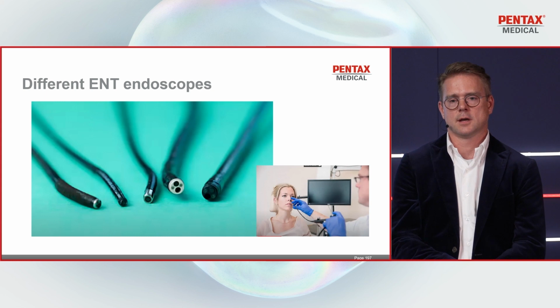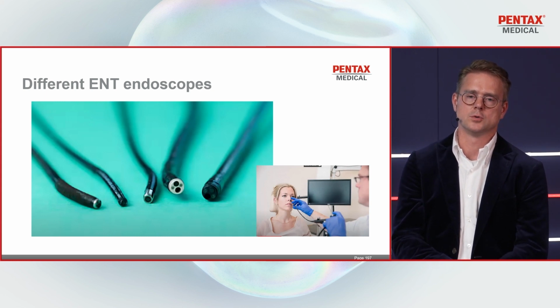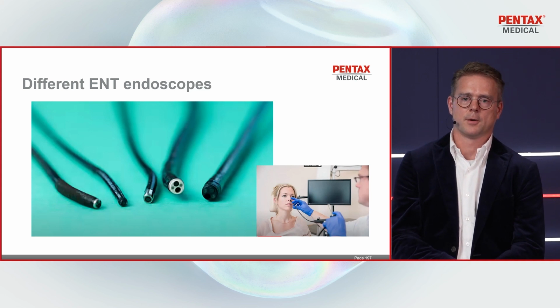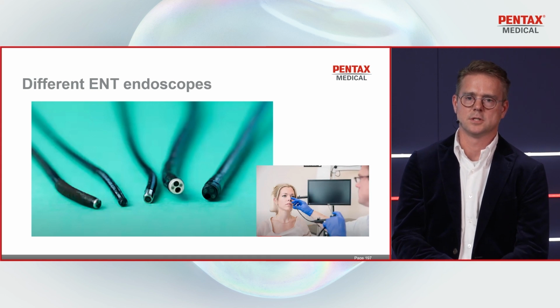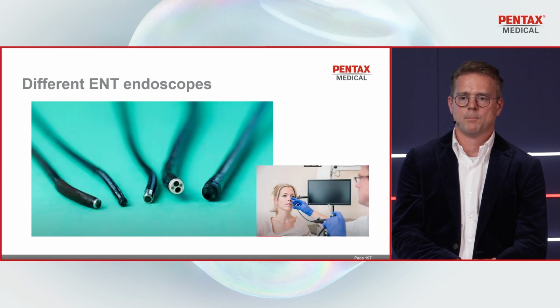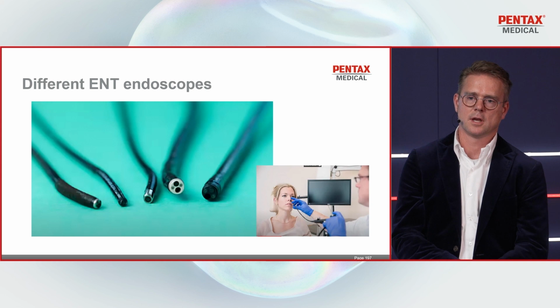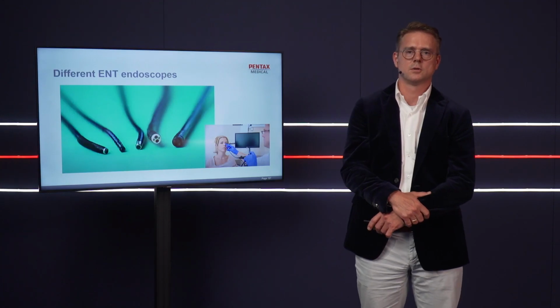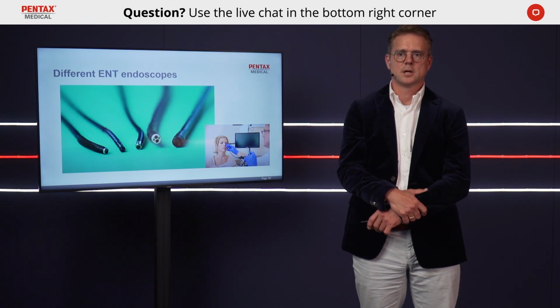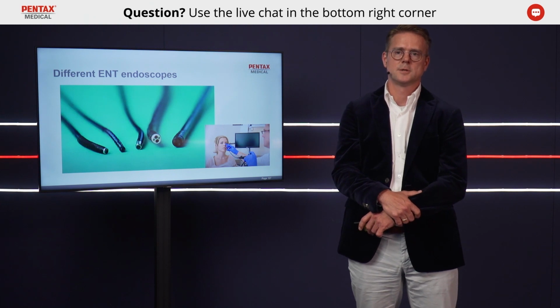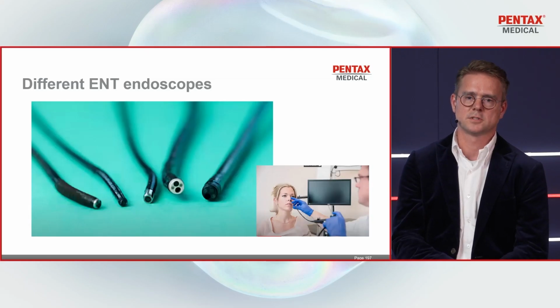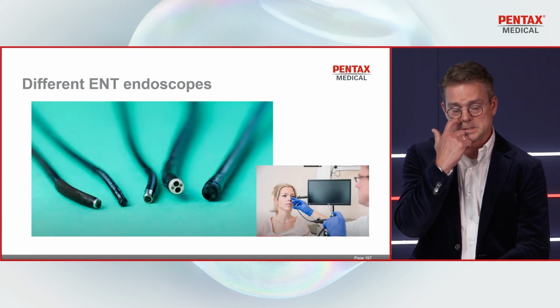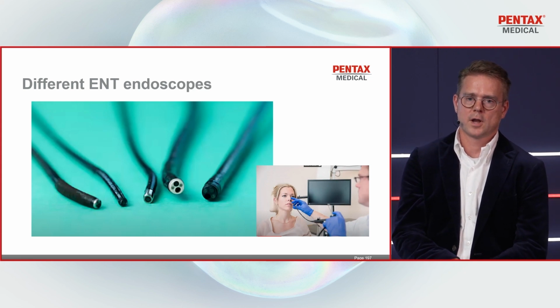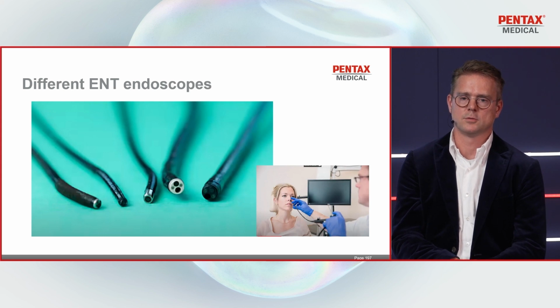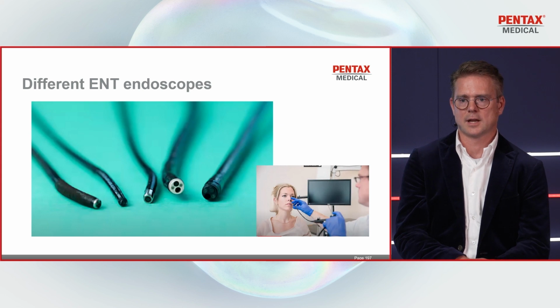When you look at ENT endoscopes, there are two main types which we are using. On the left, you see the distal end of the endoscope without a working channel, and on the right, you see an endoscope with a working channel. Most ENT doctors use the endoscope without a working channel. For example, in an afternoon, a normal ENT doctor will do about 10 endoscopy procedures in the outpatient clinic. So we use a lot of these endoscopes, and internationally there is no reprocessing consensus on how to disinfect them. Right now, UVC light is a new method to disinfect these endoscopes, and we did a study to look at that.